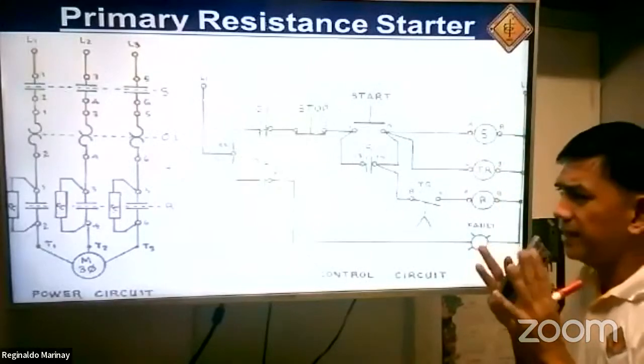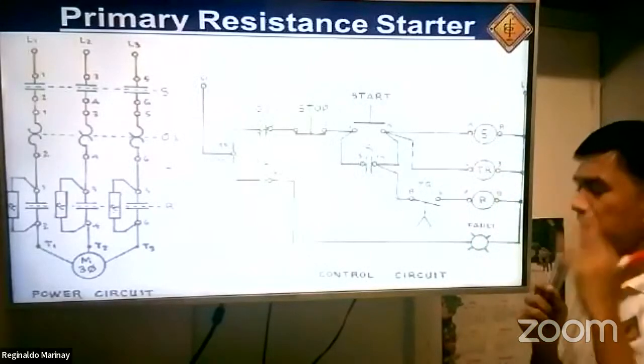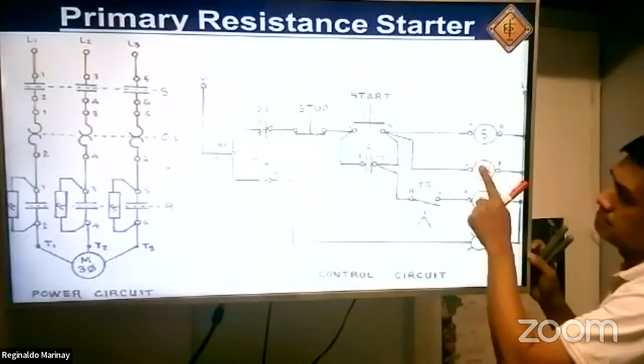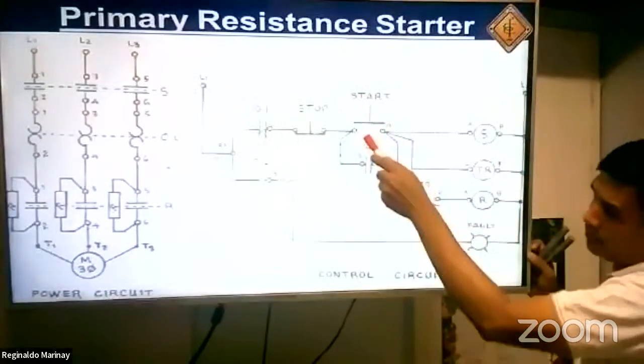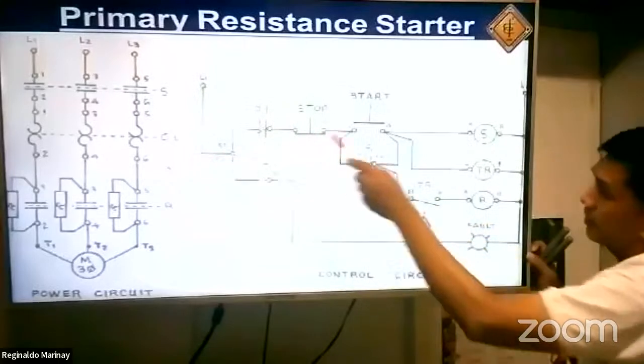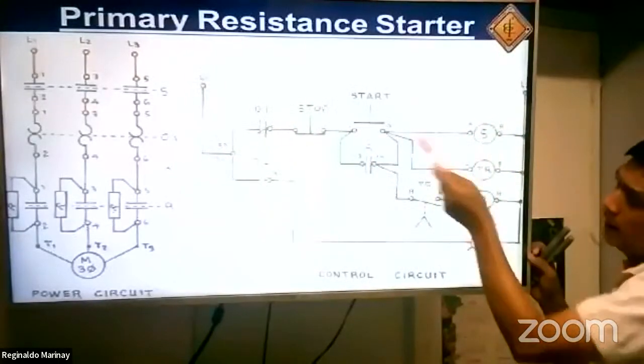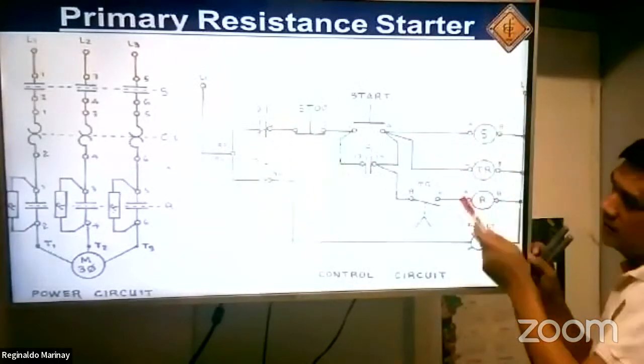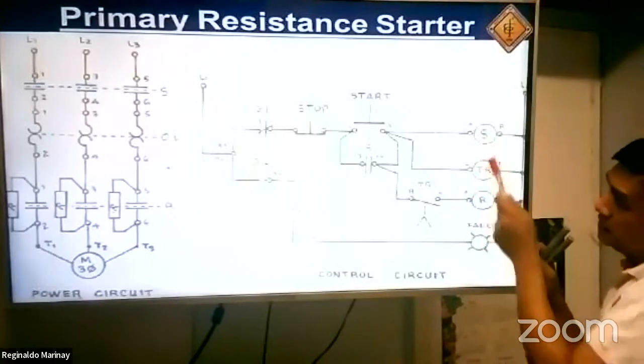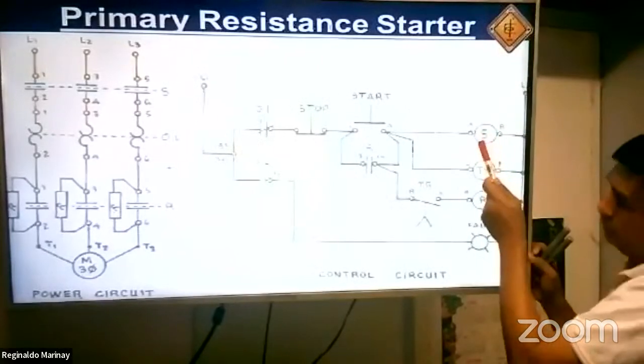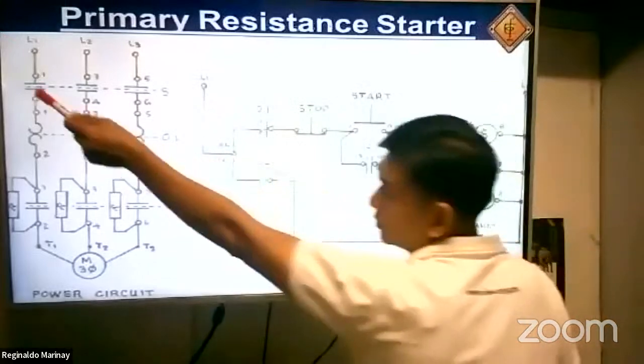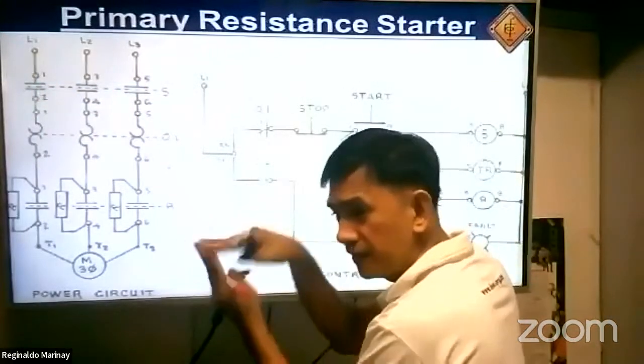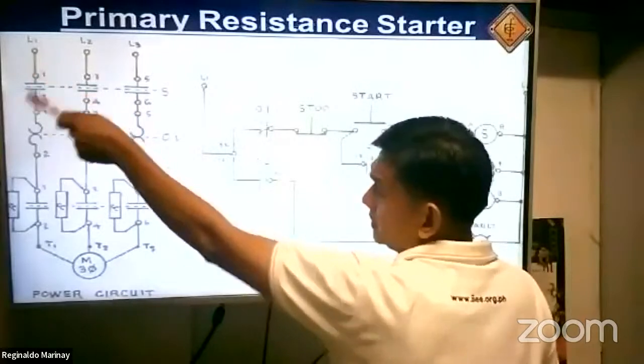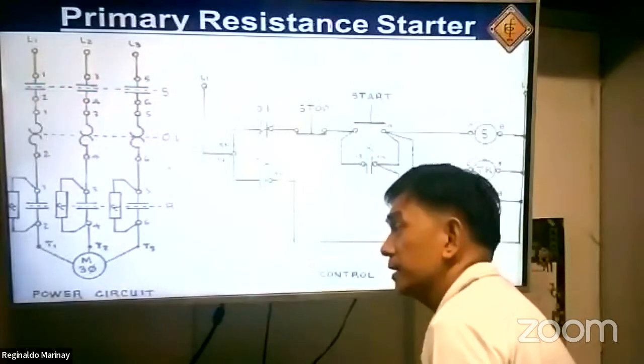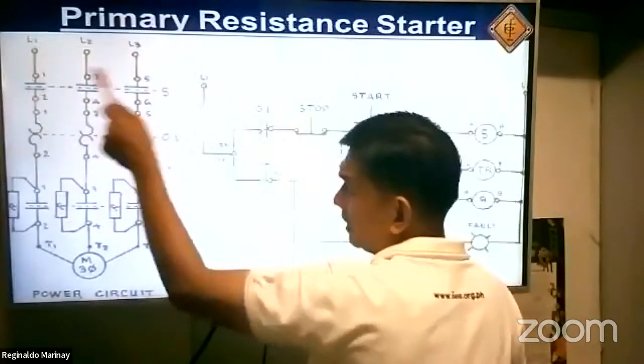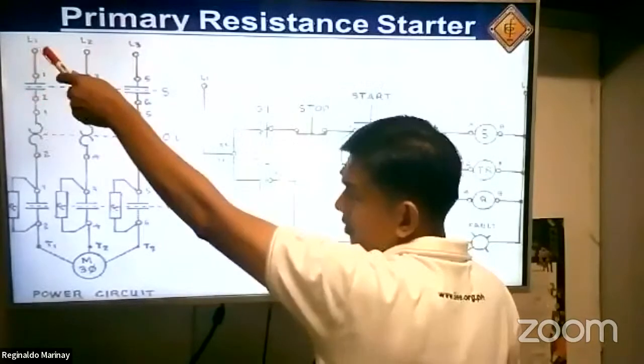Let's say I just have a 3-second setting. Once I press this push button, pop, current will flow here, energizing your S, and then your timing relay is energized. Of course, the S contacts 1, 2, 3, 4, 5, 6 will become energized simultaneously, or instantaneously.